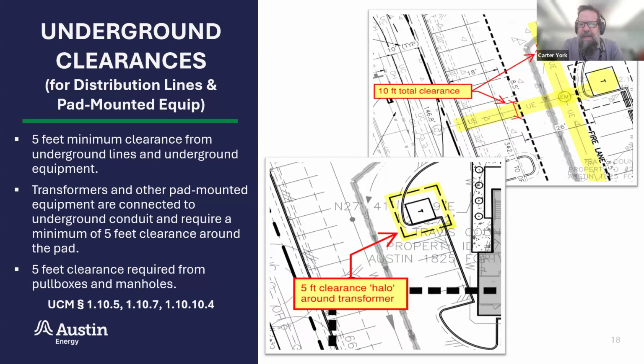On the top right image again, the circle to the left of our transformer with EM, that's one of our manholes, and that will require 5 feet clearance around that as well, as do all pull boxes and conduit. That is a very common comment that we will make. No permanent structures can be within 5 feet. That includes buildings, retaining walls. That includes permanent carport structures in parking lots.